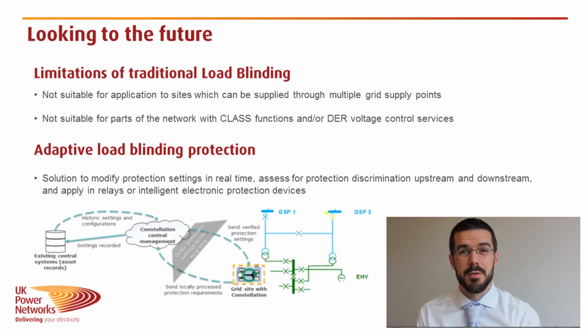At UK Power Networks, we're actively innovating to overcome these challenges in the future. In a digital substation, it's possible to download the protection settings, modify them, and then to reload them back into the relay. And this is something that would enable the substation to dynamically change its protection settings configuration to cope with a dynamic change in the network in the future.